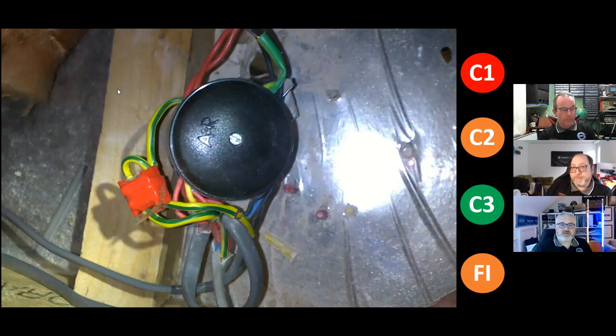Okay, so let's debate the issue then. 78% have said C2. Okay, C2, potentially dangerous, urgent remedial action required. So what's the potential danger then? So I would argue terminations straight away. The terminations aren't secure because now they will be secure inside the junction box via the brass screws, but the actual unit, as you can see from that, is just floating.